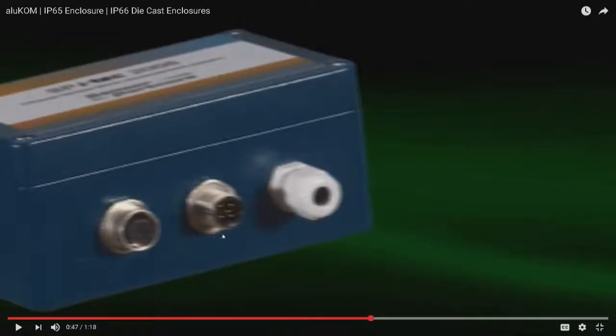You see here, there are three types of connectors. This one is a cable gland. We have this plug, and then it has a ferrule inside. Then if you select the proper type of rubber gasket which comes with it, and then when you turn it, something is squeezed and it holds hard. There is a tapered portion and it holds hard. Important is you must always select the correct type of washer there, otherwise it is useless.